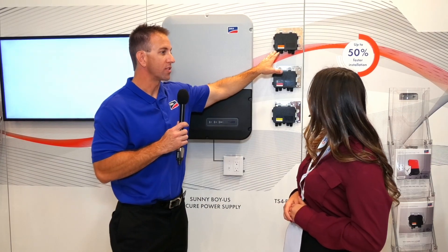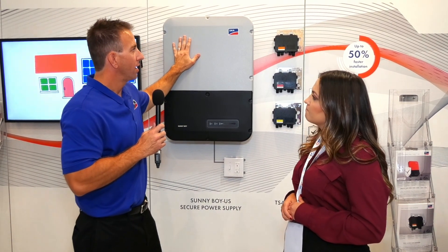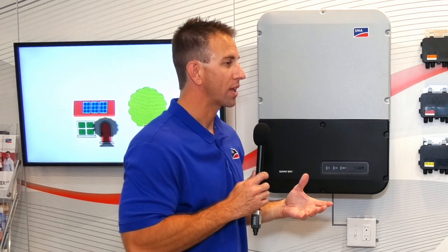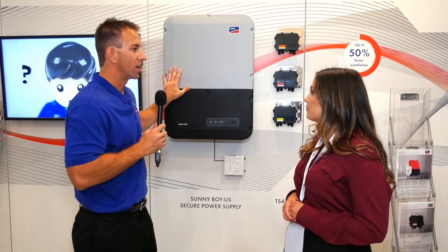Paramount among these new enhancements this year is the TS4RF. This is a module level device that pairs with the Sunny Boy and allows for module level shutdown. It is SunSpec compatible, works on the SunSpec communications protocol, and is the fastest, easiest way to achieve compliance with NEC 690.12 module level shutdown.